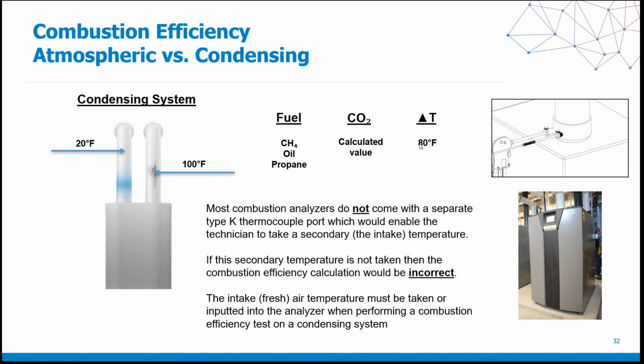So as I mentioned, my industry has led some of you astray by not giving you that secondary type K thermocouple port. You need that port, or you need a way to account for a secondary temperature. And in this case, when you're looking at combustion efficiency of a condensing system, that secondary temperature is the outdoor air. So that needs to be accounted for.